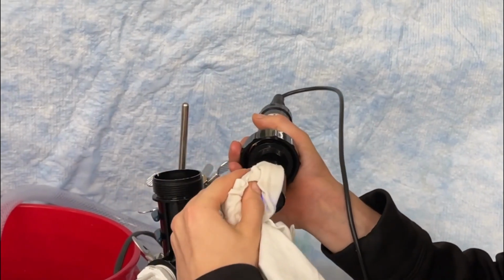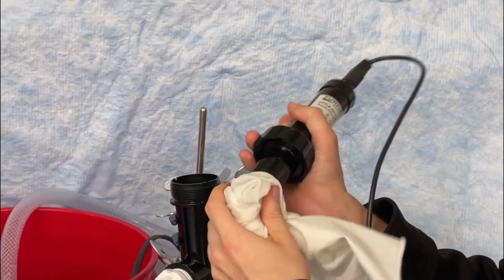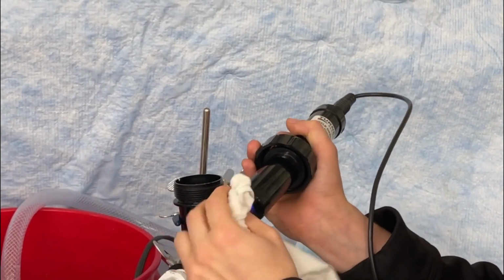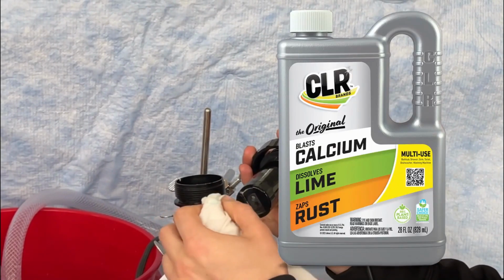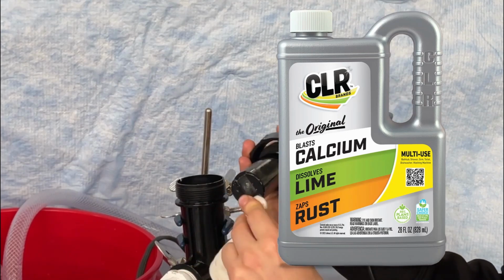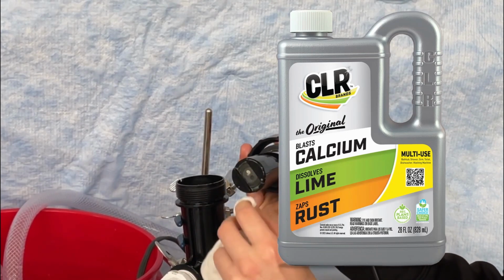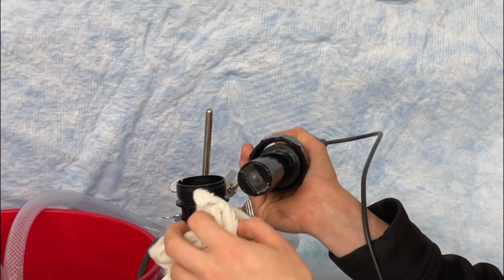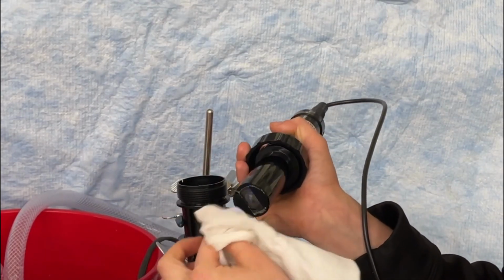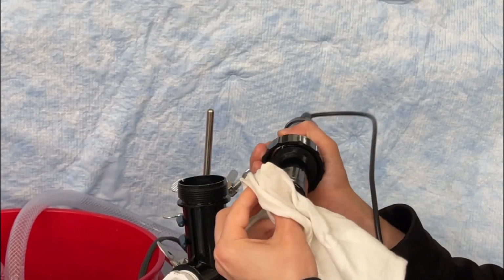Sometimes it takes quite a considerable effort to remove all of the debris from an LD2. An alternative cleaning agent that you can use would be CLR, which you can get at any hardware store. The process is the same as soapy water.